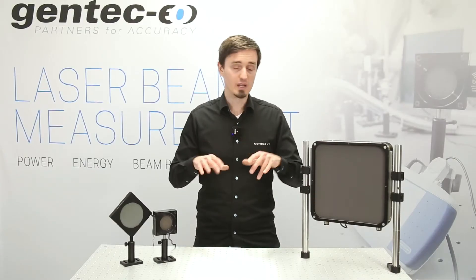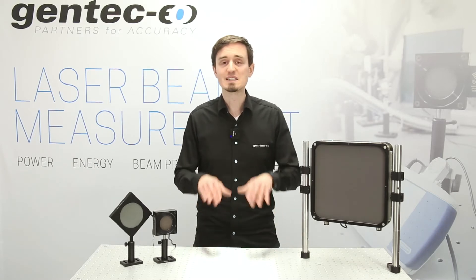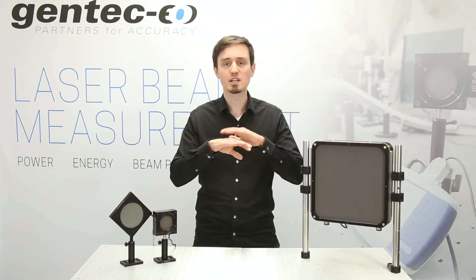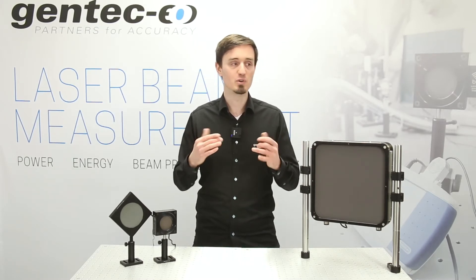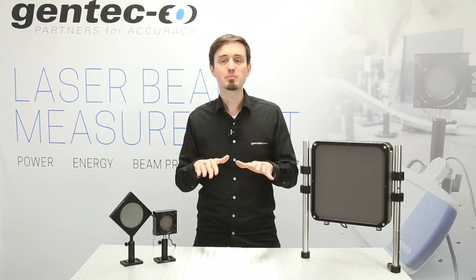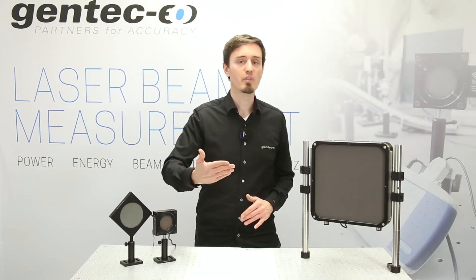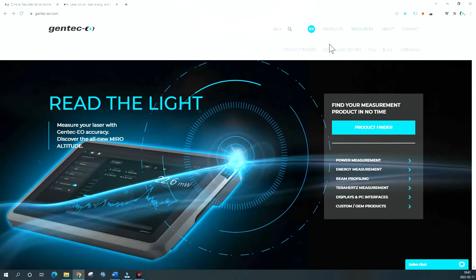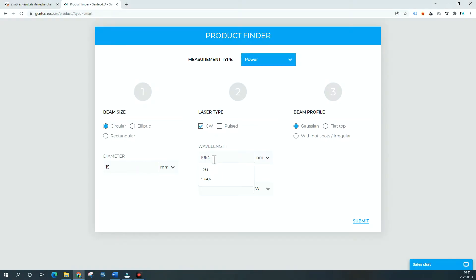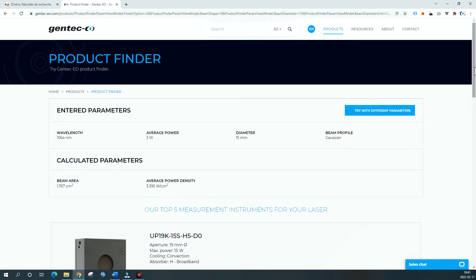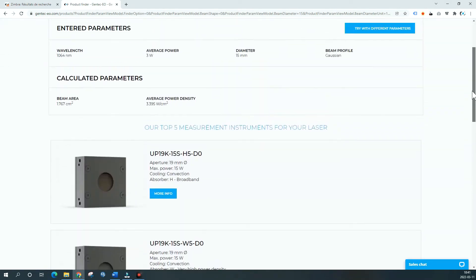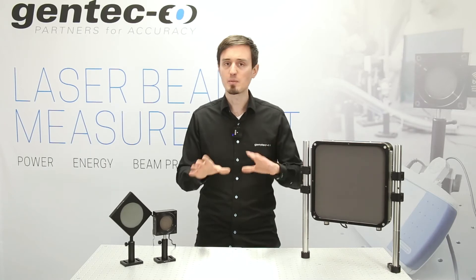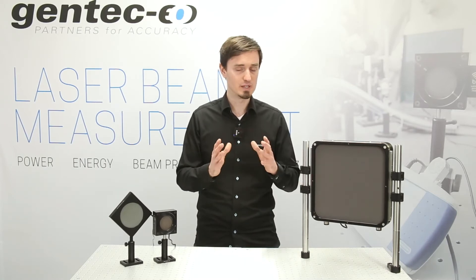With a Gaussian beam profile, the intensity is doubled in the center of the beam. Divide your average power by the area covered by your circle of diameter 1/e², then multiply this value by 2, and compare that to your specified damage thresholds in watts per square centimeter. Or simply use the Gentec EO online product finder, which can make all those calculations for you. In case your laser beam shows hot spots or you're unsure about the profile, it's common to apply a safety factor of 3 to this calculation.